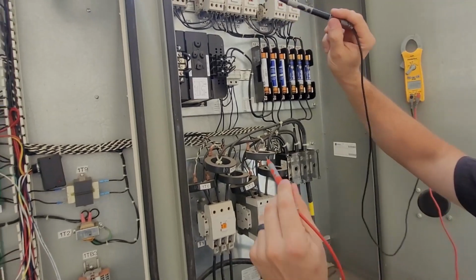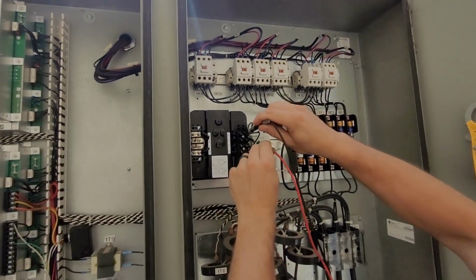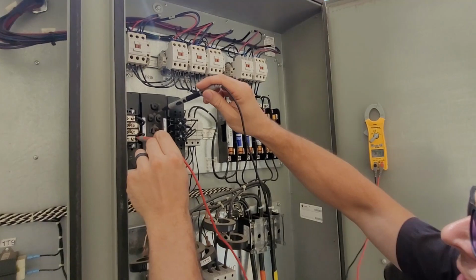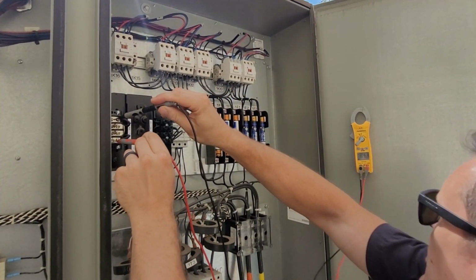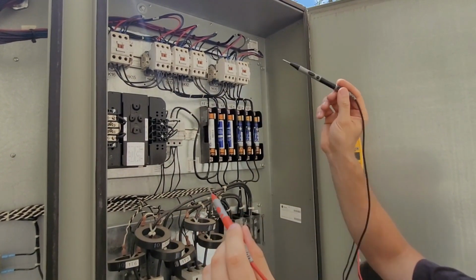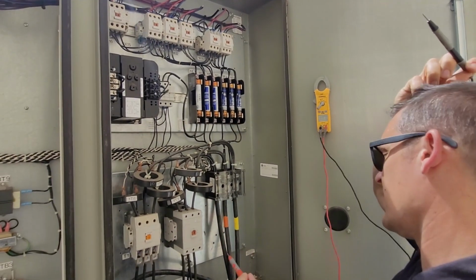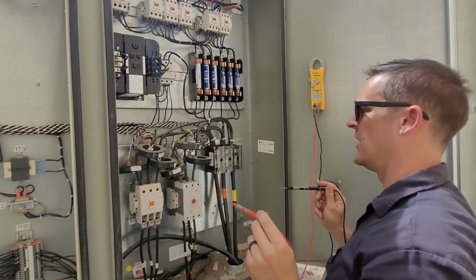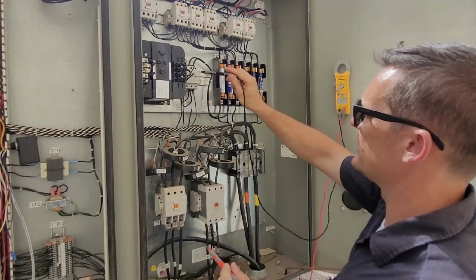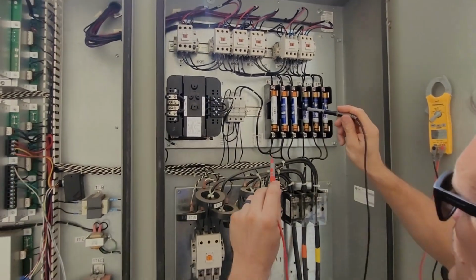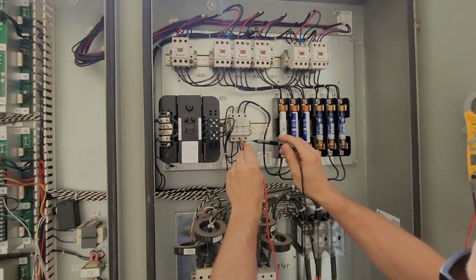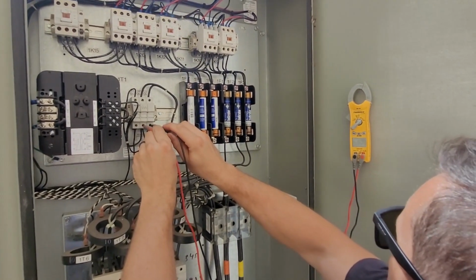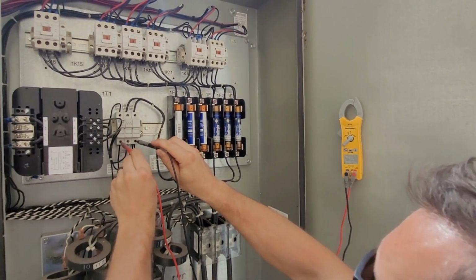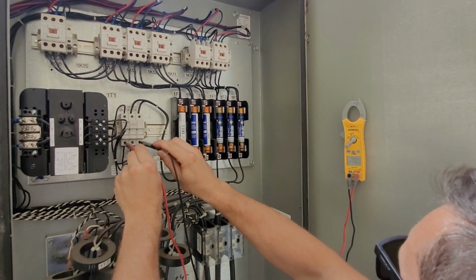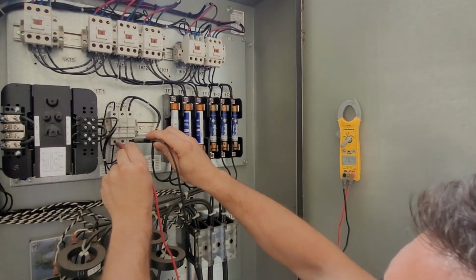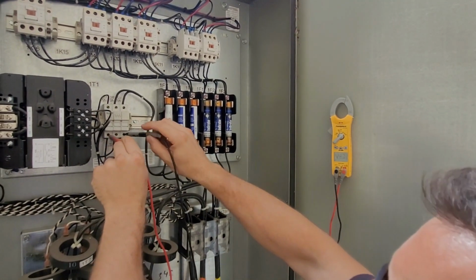So then I'm checking this big transformer here. This one's got 480 coming in, and on the low side it's got 120. So it's making power just fine. There's nothing wrong with the coils inside that transformer. And so then the only fuses left in the whole thing are these 3 fuses right here. So I like to check between them. So here I've got my 480, but when I go here I get 280. So that's different, right? It's basically 277, I guess.